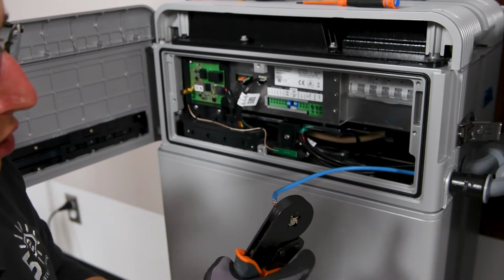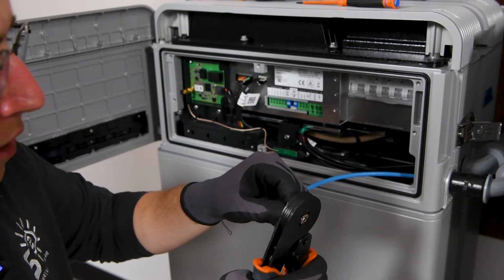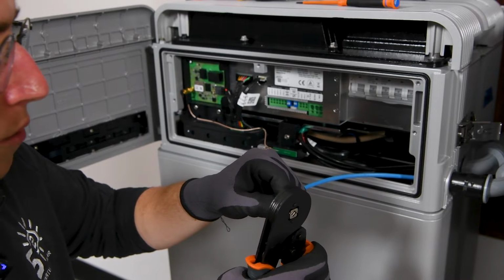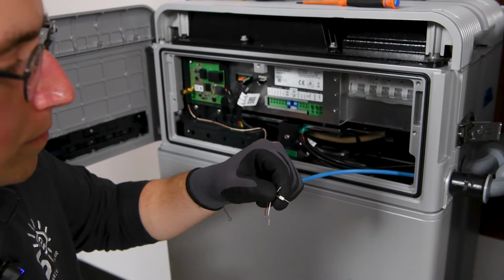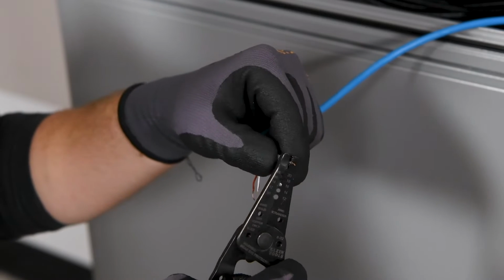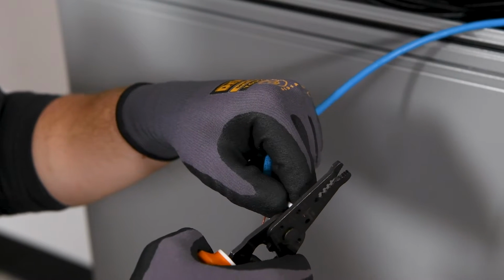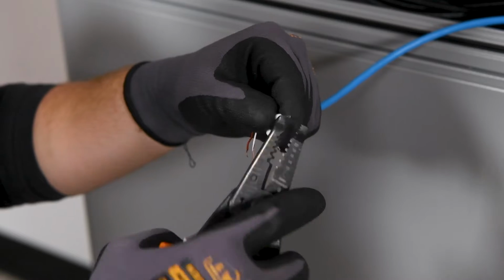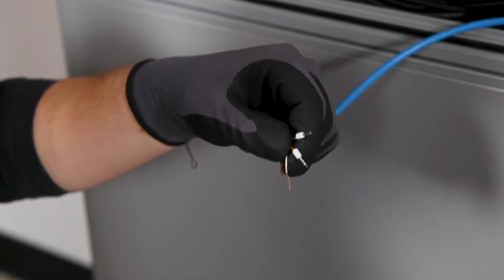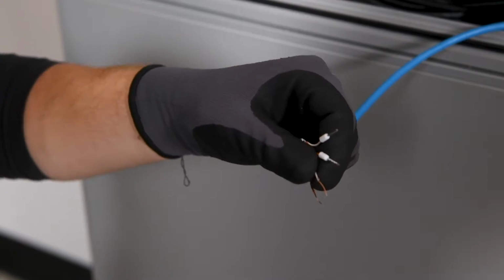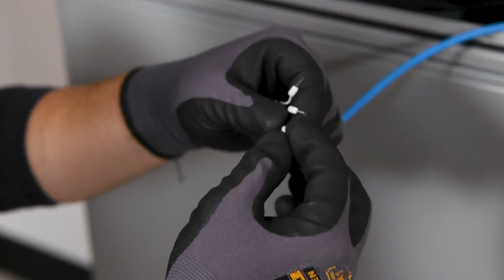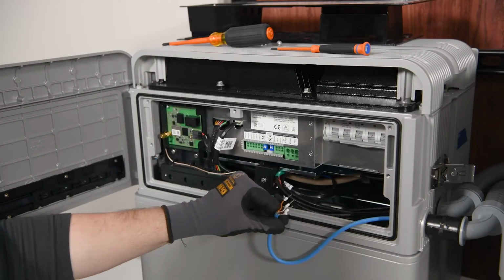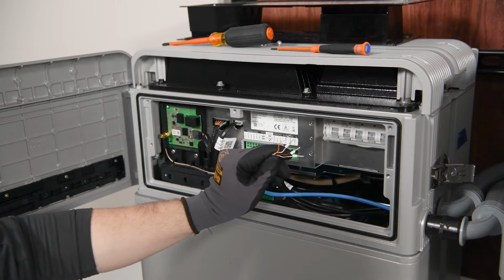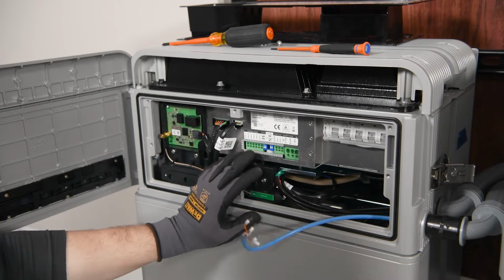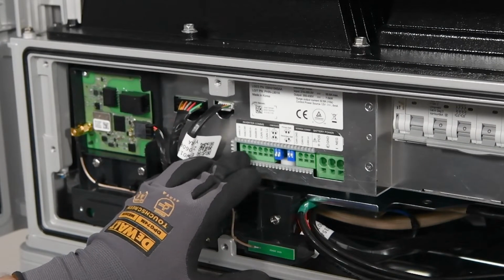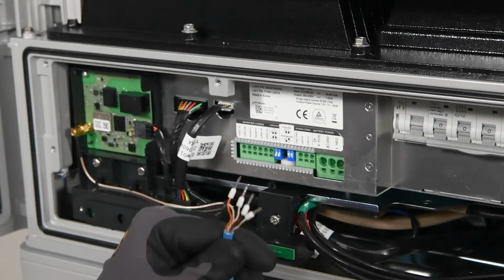So I'm just using some very small ferrules here and making sure that they are biting on properly to the cable. If you have any excess cable sticking out of your ferrule, you can just take some wire cutters and clip it away to the top of the ferrule like that and make everything nice and clean. So now that we have our 4 communication cables, our 4 conductors ferruled, we're going to connect to the inverter comms ports on the LG Prime.